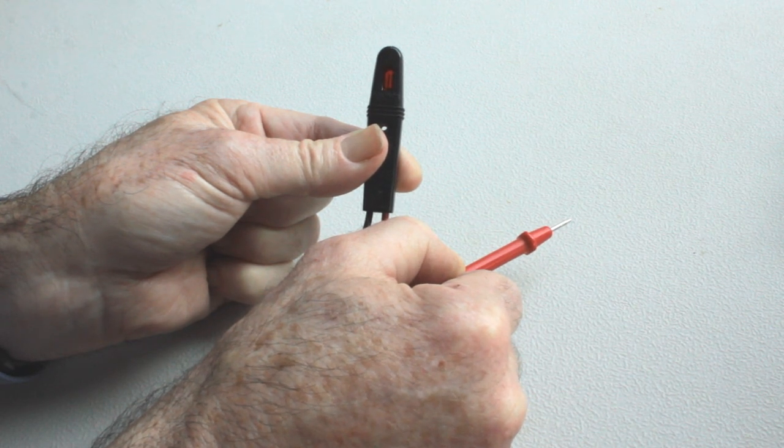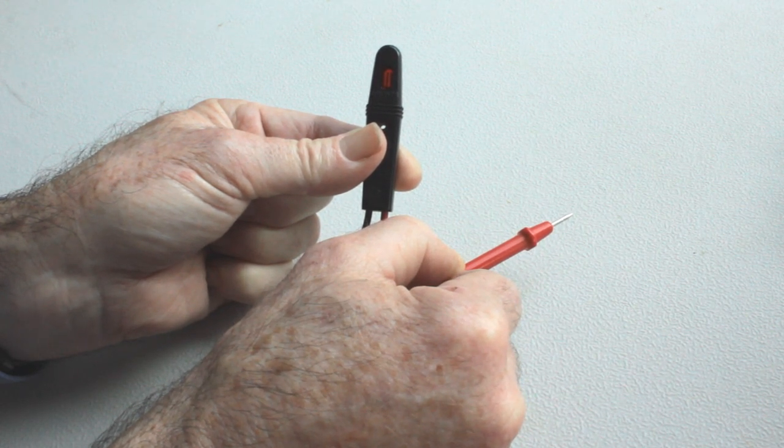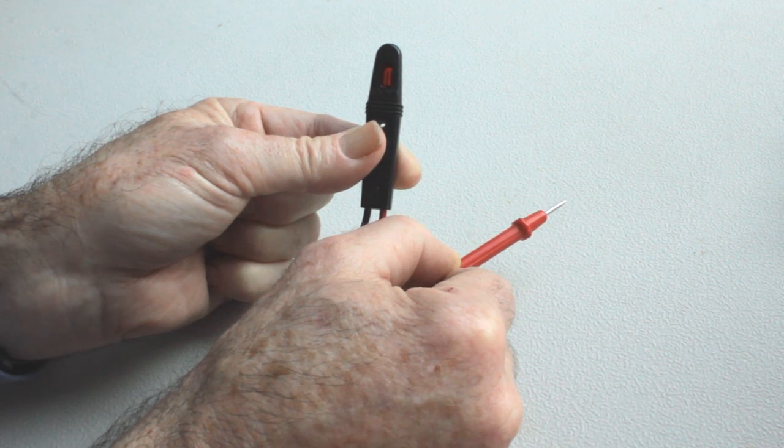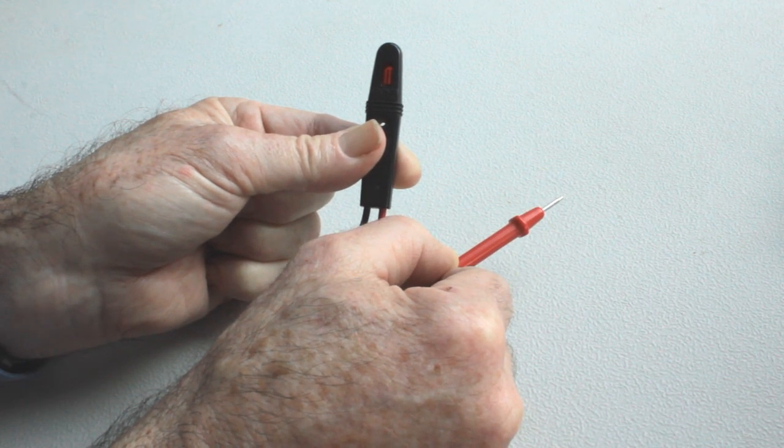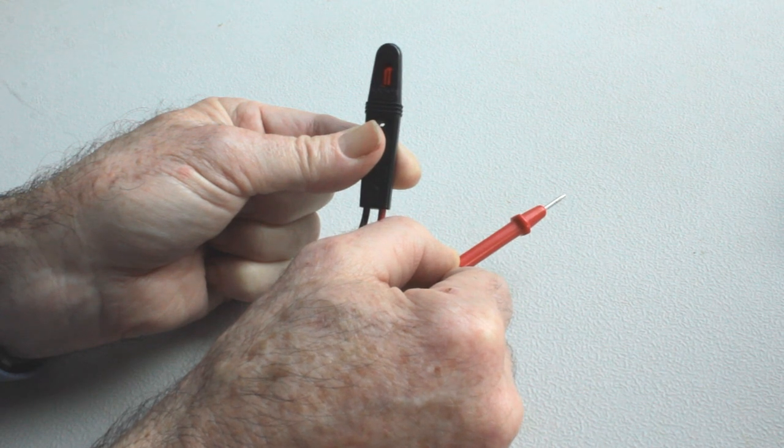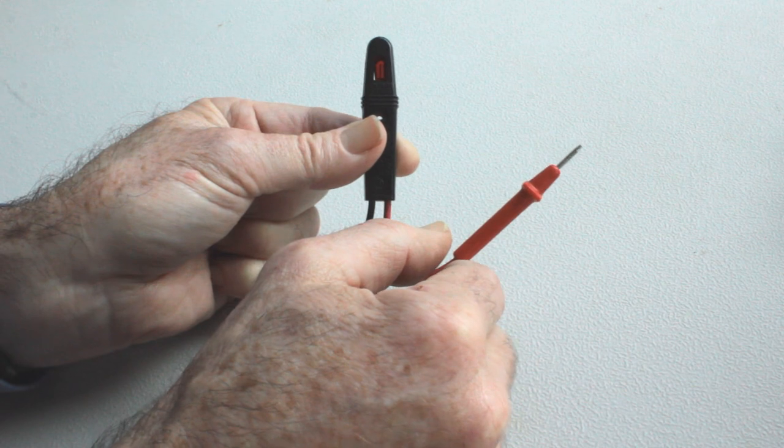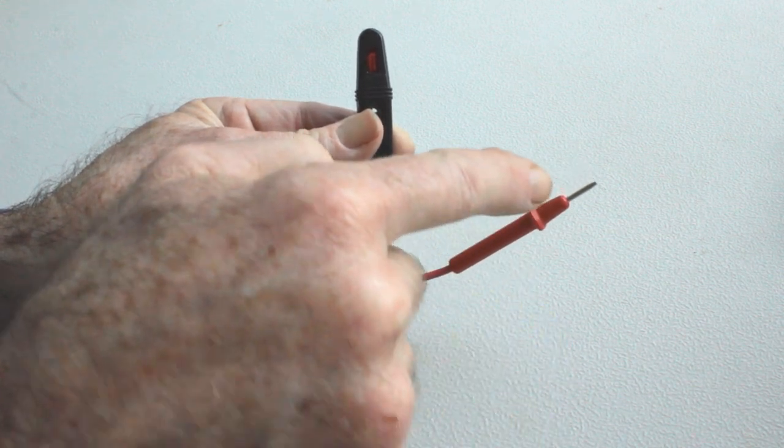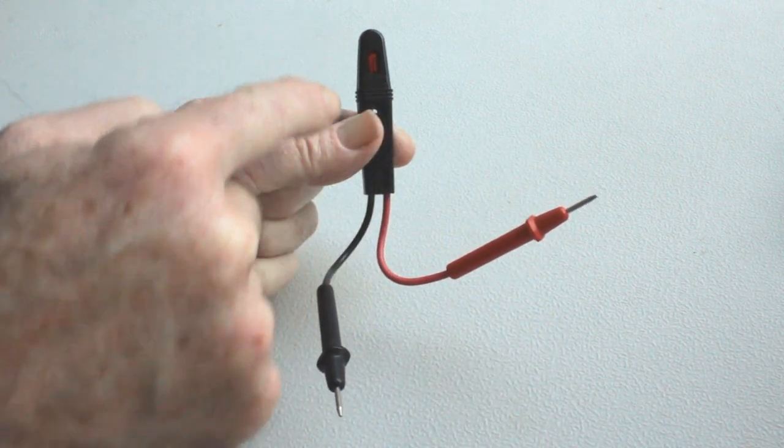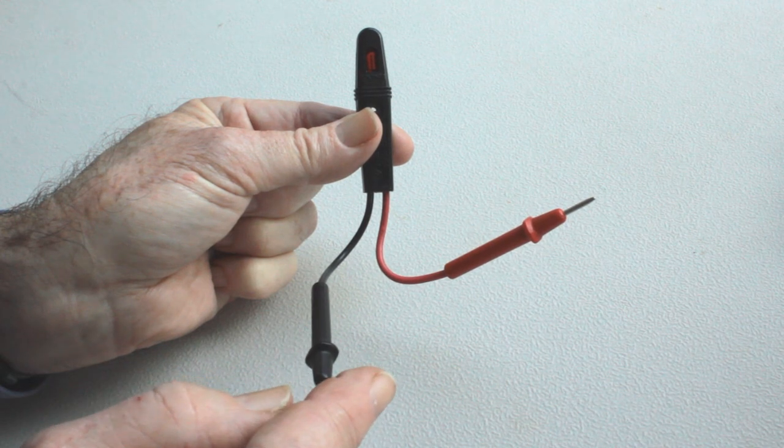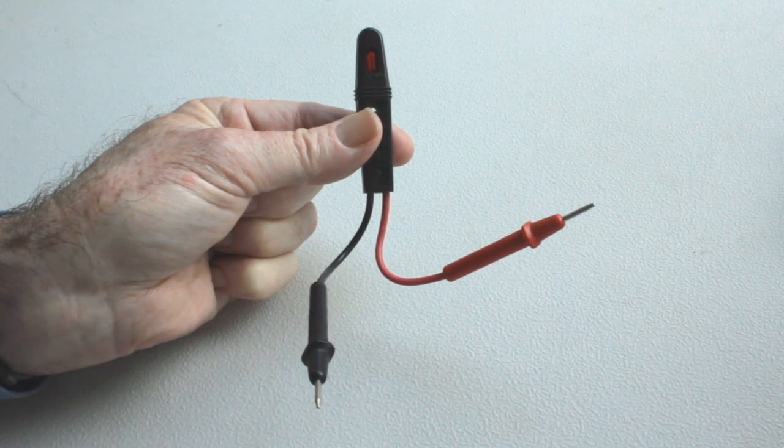The resistance through that tester and its bulb is so high that I would not feel anything in the way of a shock, even though a little bit of current would be flowing through the palm of my hand and through me to the ground.